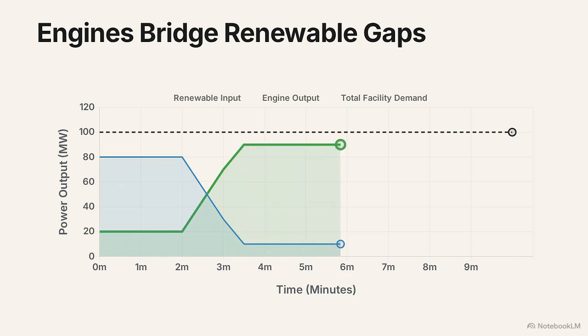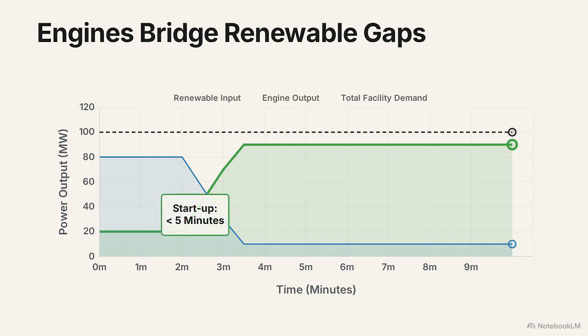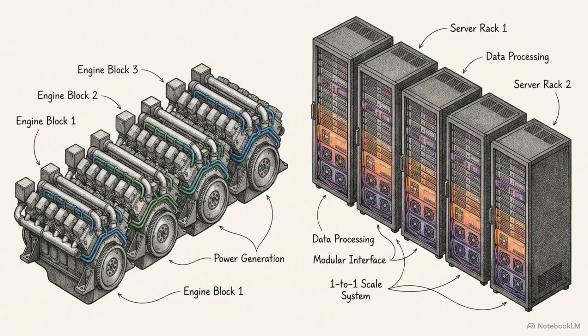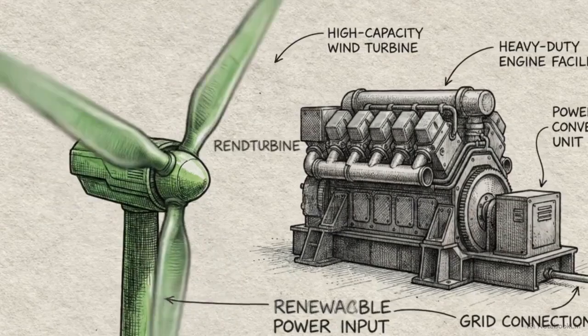Corporate renewable procurement relies heavily on wind and solar power purchase agreements, which introduce physical intermittency into the facility's power supply. Captive engines bridge this gap through rapid load following. As renewable input drops, the engine immediately increases output to maintain a stable server supply. These systems start in under 5 minutes, ramping output at over 40% per minute. Engines deploy in modular increments of 7 to 26 megawatts. This allows the power plant to scale alongside new server racks, preventing wasted capital expenditure. Captive engines provide the load-following capacity needed to make high-penetration wind and solar power mathematically viable for an isolated microgrid.